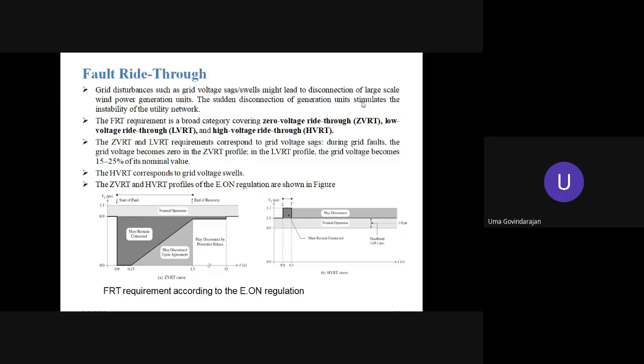Okay, the zero voltage ride-through and LVRT requirements correspond to grid voltage sags. This is normally a problem that can occur during grid faults. So the grid voltage becomes 0 in the zero voltage ride-through profile, and in the LVRT profile the grid voltage becomes 15 to 20% of its nominal value.